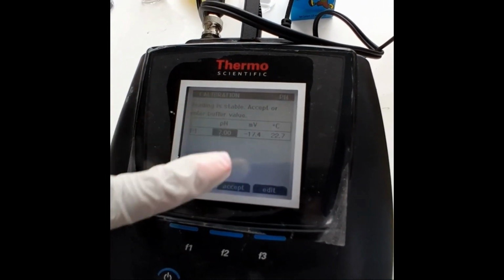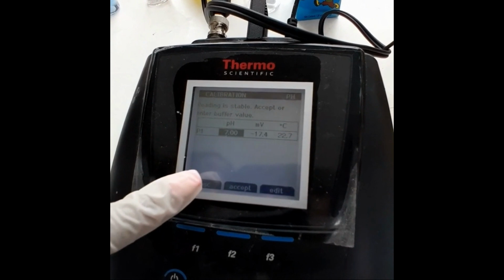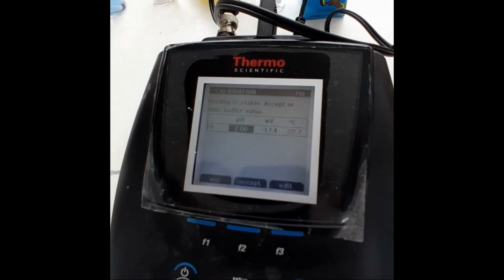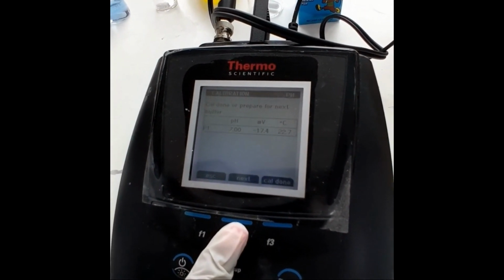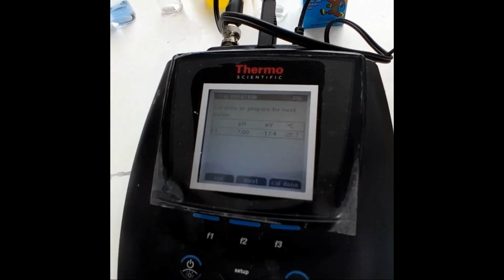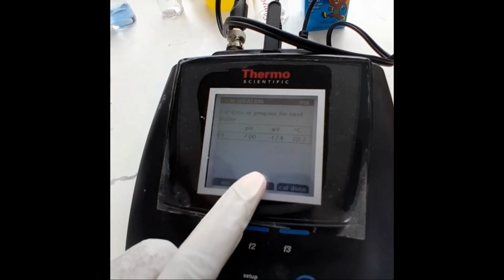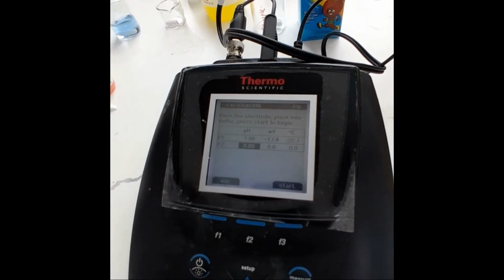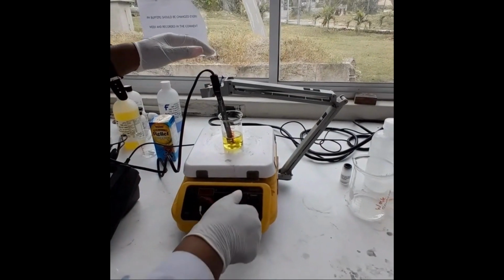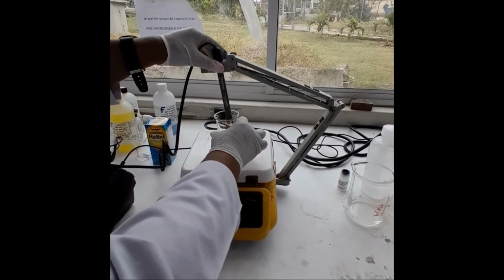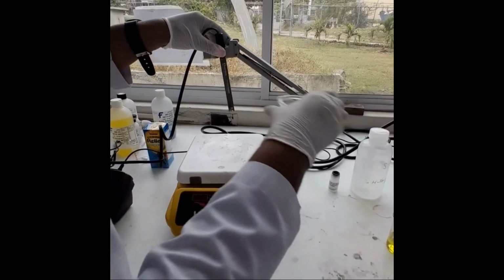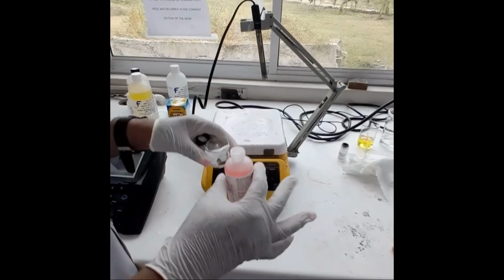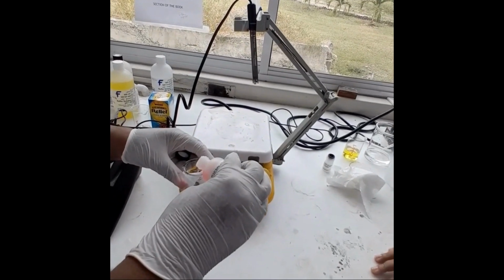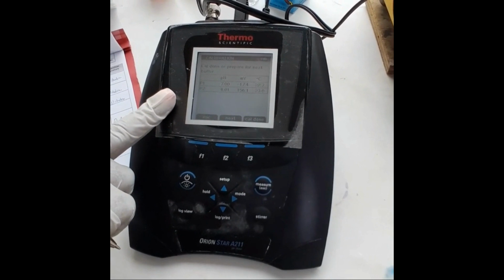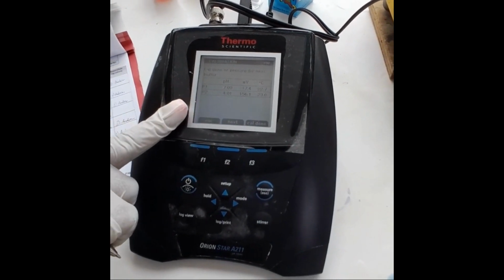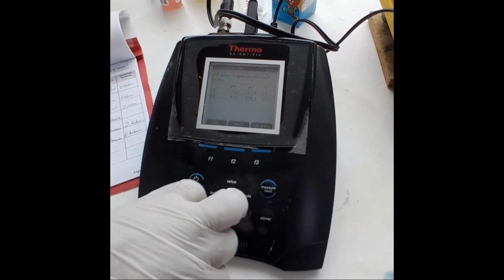If the reading is stable, accept and enter the buffer value. So it's reading 7, so we're going to accept it. Now that we have accepted it, we are going to move on to our next buffer. So we press F2, next, F2. All right. To remove, you can turn off your stir bar, remove your pH probe, and then we will rinse and blot dry again. So we're going to pour buffer 4 now and repeat the same steps as before. Now we have our 2 buffers, buffer 7 and buffer 4. Now that we have finished, we'll press calibration done.